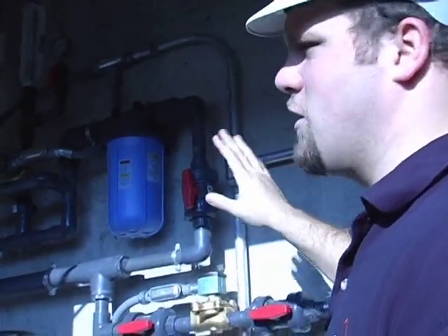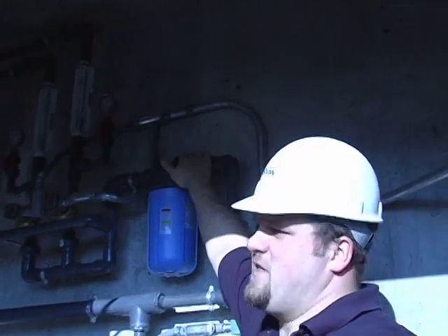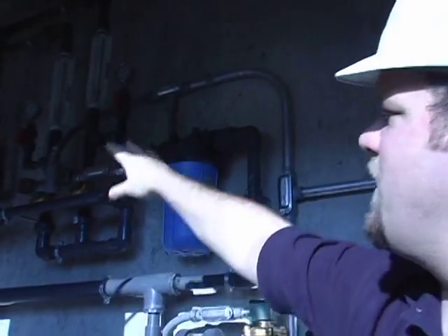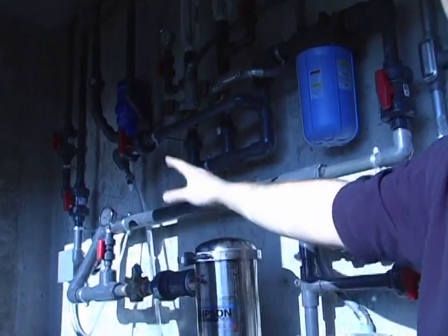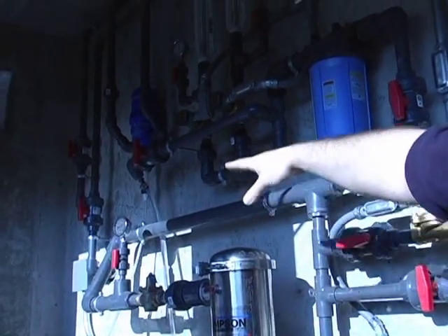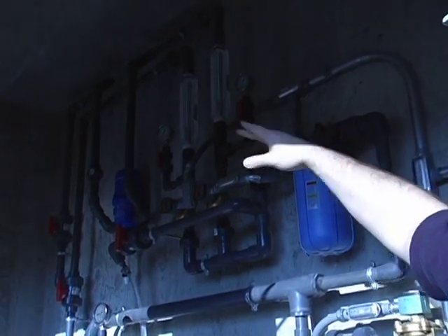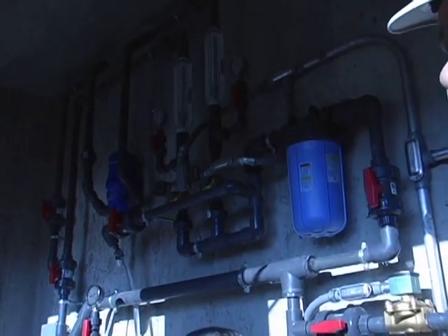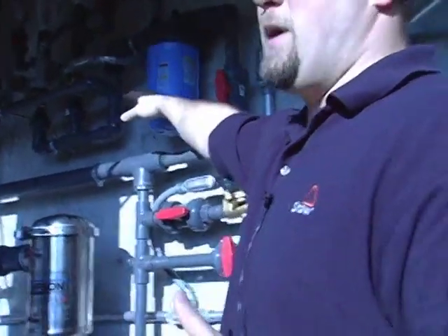Anytime you do any maintenance where you're opening up lines, you might get some air in the lines. There's this red bleeder button on top here. You can bleed the filter. Same goes with the dosatron unit. If air ever gets in the hose, if the tank runs dry and there's air in the hose, there's a little black button on top of that dosatron unit where you can hold that down and it'll bleed the air out of your dosing unit there. So as we move on in this piping run, I'll just step right here.